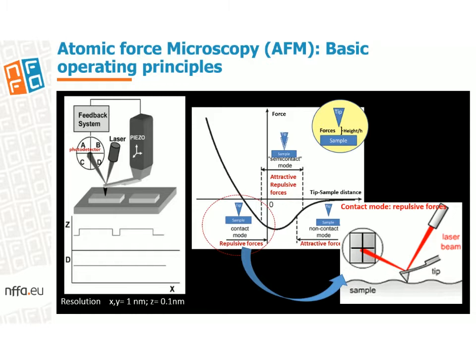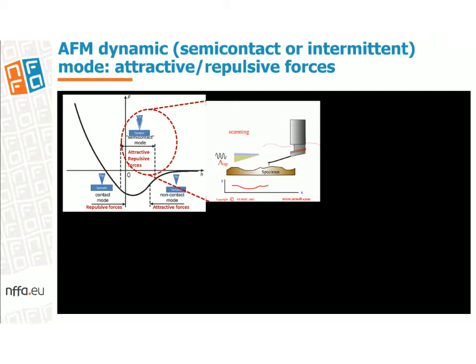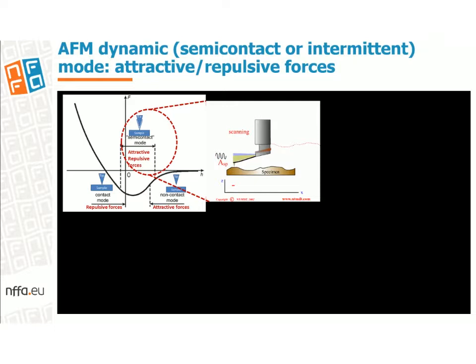The first development of the AFM was based on measuring the repulsive forces by contacting the sample with the tip. Since contact AFM mode can cause substantial damage to soft samples, a semi-contact AFM mode was developed. Such intermittent contact AFM mode is accomplished firstly by oscillating the cantilever near its resonant frequency and then by bringing the tip towards the sample until it begins to slightly tap the surface, reducing its oscillation amplitude.